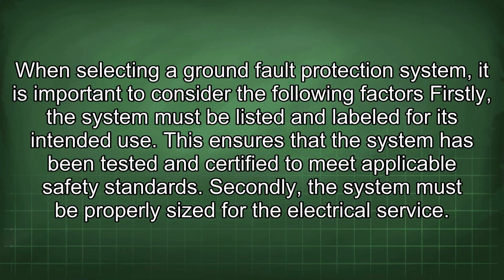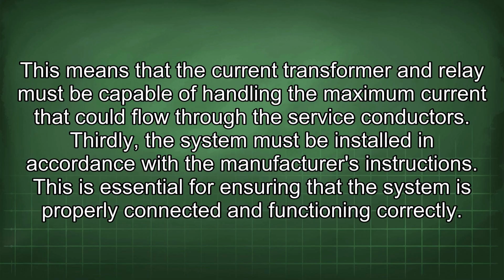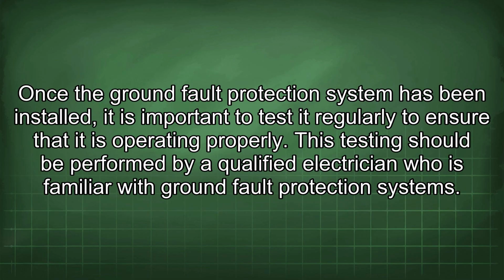Secondly, the system must be properly sized for the electrical service. This means that the current transformer and relay must be capable of handling the maximum current that could flow through the service conductors. Thirdly, the system must be installed in accordance with the manufacturer's instructions. This is essential for ensuring that the system is properly connected and functioning correctly. Once the ground fault protection system has been installed, it is important to test it regularly to ensure that it is operating properly. This testing should be performed by a qualified electrician who is familiar with ground fault protection systems.